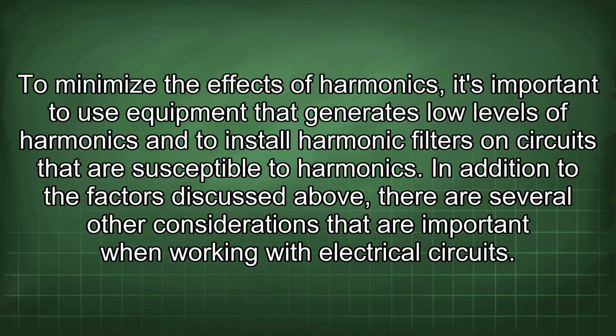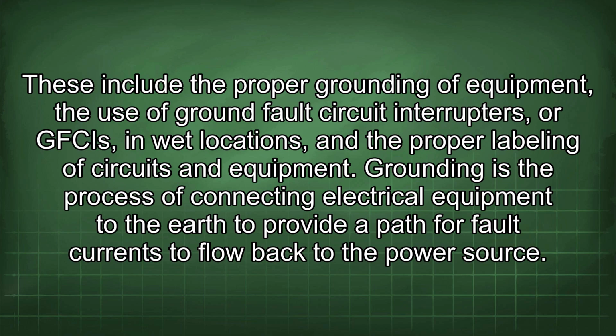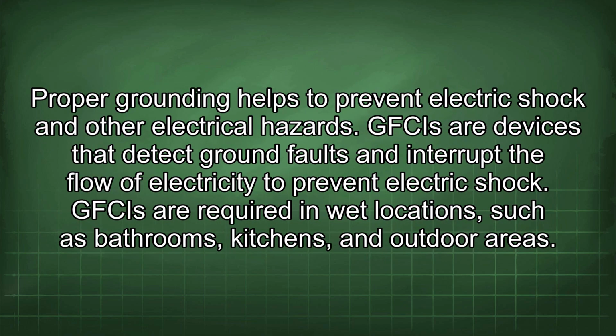In addition to the factors discussed above, there are several other considerations that are important when working with electrical circuits. These include the proper grounding of equipment, the use of ground fault circuit interrupters, or GFCIs, in wet locations, and the proper labeling of circuits and equipment. Grounding is the process of connecting electrical equipment to the earth to provide a path for fault currents to flow back to the power source. Proper grounding helps to prevent electric shock and other electrical hazards.